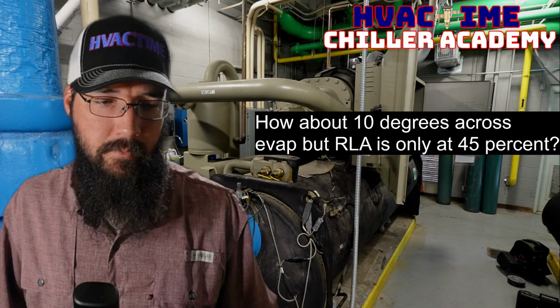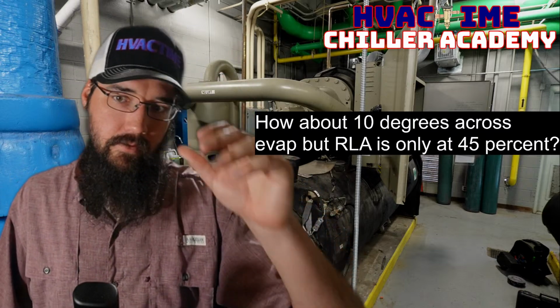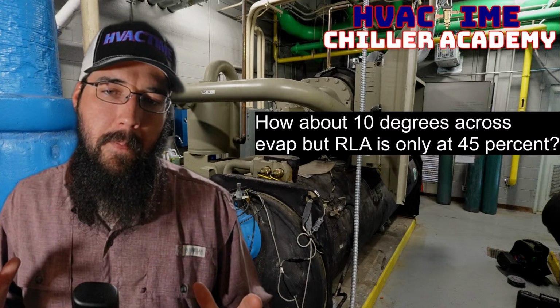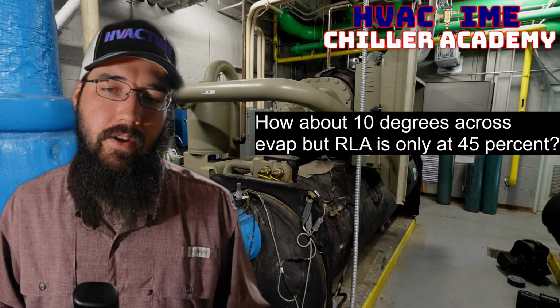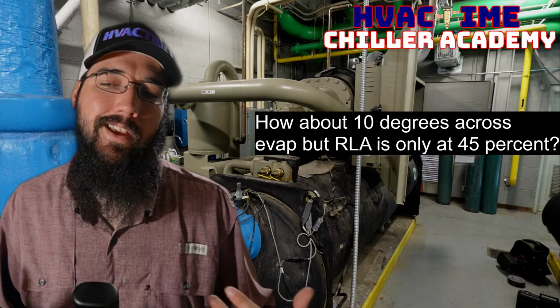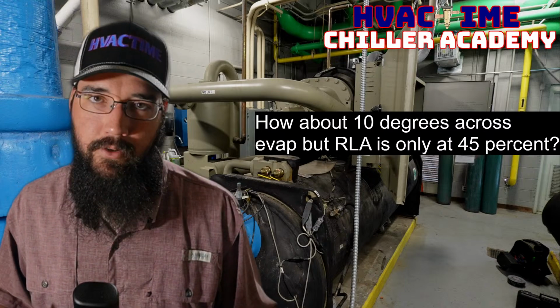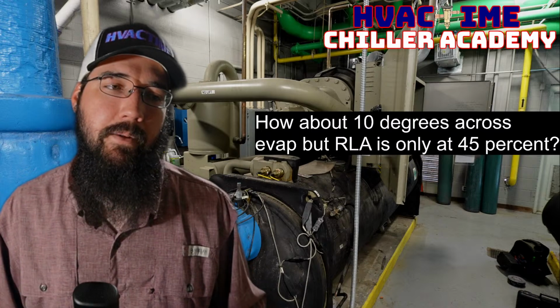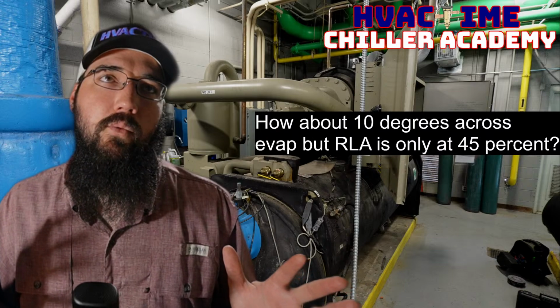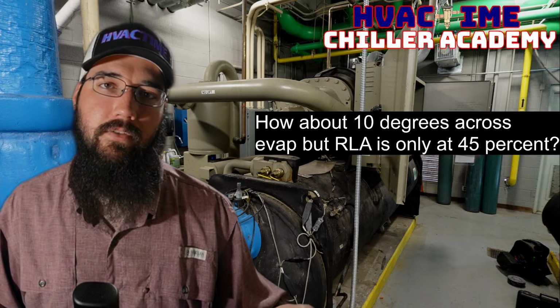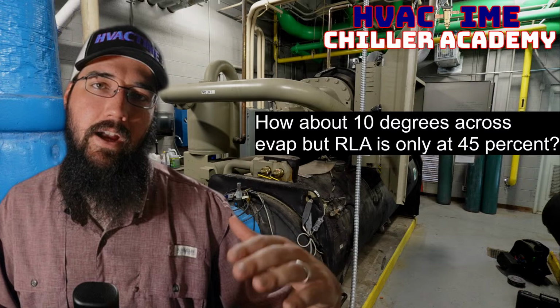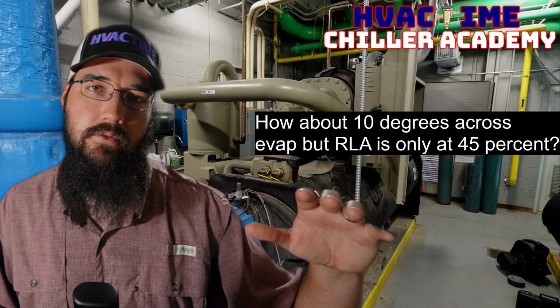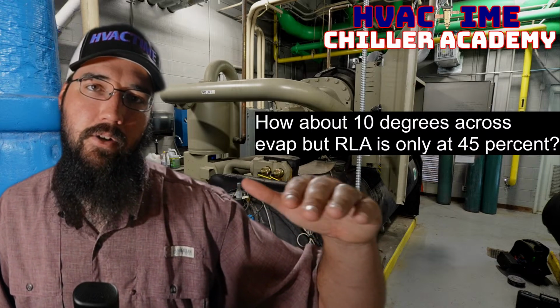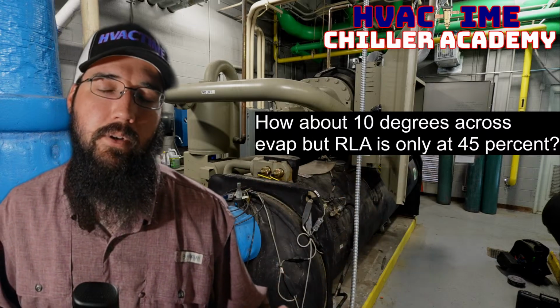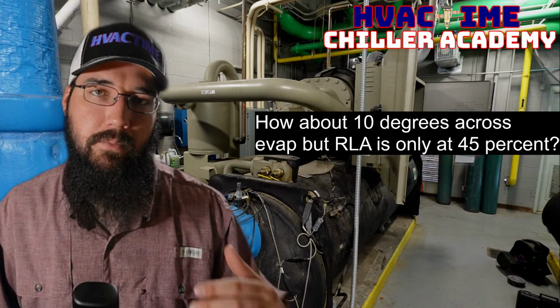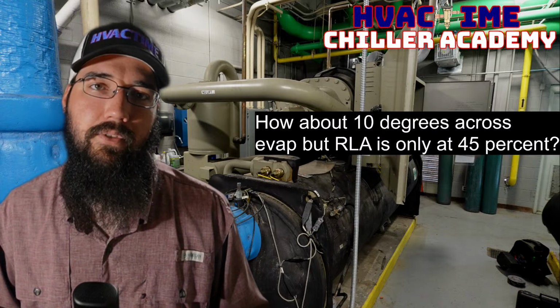Okay, let's talk about this one a little bit. We have to be careful. So, how about 10 degrees across the evap, but RLA is only at 45%? Now, this is in the context of the chiller being loaded or not loaded. I've recommended in the past that for a chiller designed for a 10-degree drop across the evaporator, if I'm operating at that, making set point, and my entering water is high enough to be 8 to 10 degrees, or at least 8 degrees above that, then I consider I've got a pretty decent load, and I should be able to get a pretty good analysis of how the chiller is operating.